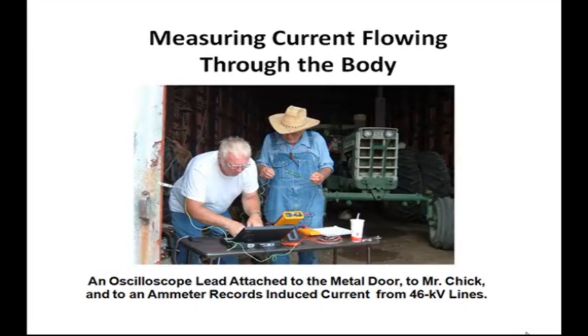The scope meter recorded 1.45 volts RMS in the meter mode. Magnetic field was 4.2 milligauss under the line. Mr. Chick was sensitive to the electric shocks to his hands. Current flowing through the lines 11.9 meters above the earth was 24.3 amperes at the time. Maximum current had been 290 amperes according to company records.